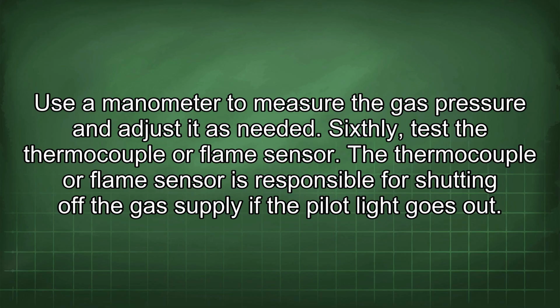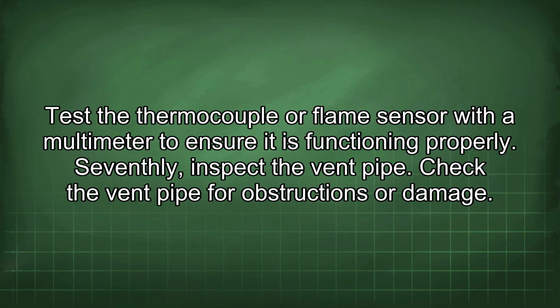Sixthly, test the thermocouple or flame sensor. The thermocouple or flame sensor is responsible for shutting off the gas supply if the pilot light goes out. Test the thermocouple or flame sensor with a multimeter to ensure it is functioning properly. Seventhly, inspect the vent pipe. Check the vent pipe for obstructions or damage.